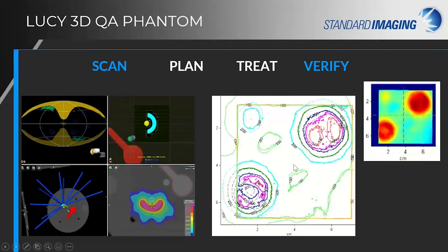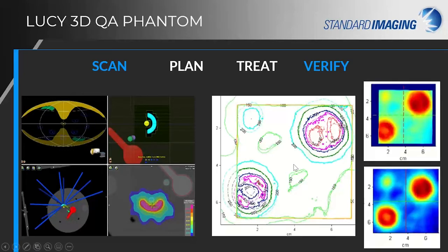So here, for example, we have images of the C target planned for delivery, which is verified with film and microchamber. And here we have a couple of the inserts for our targets from the multi-MET insert that are planned and then verified using the criteria of 2% 2 millimeter, passing over 99%, and the dose agreement less than 2%. So very, very good, rigorous tests.